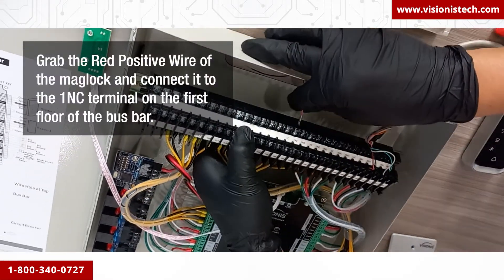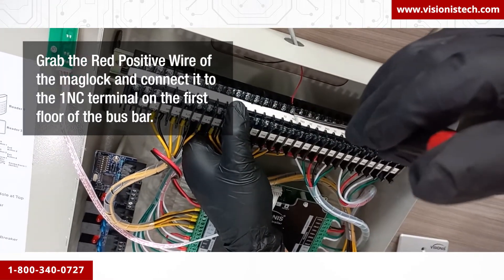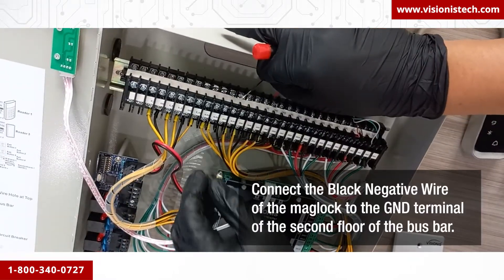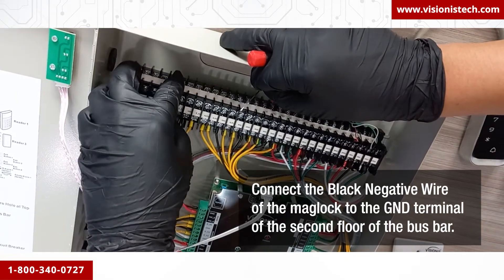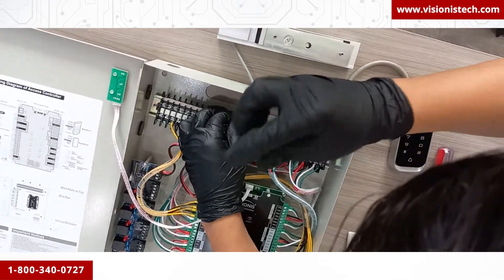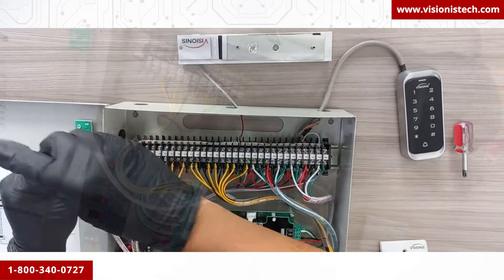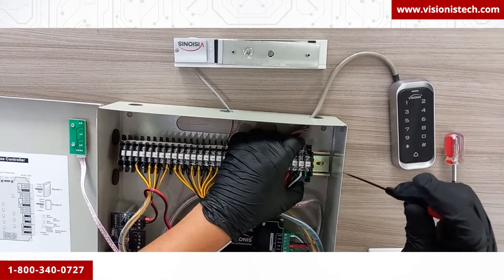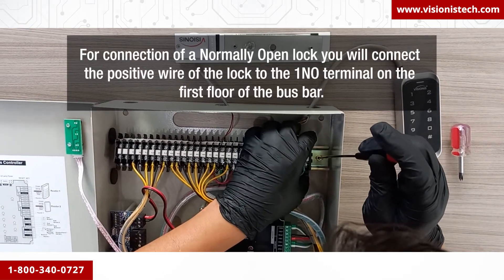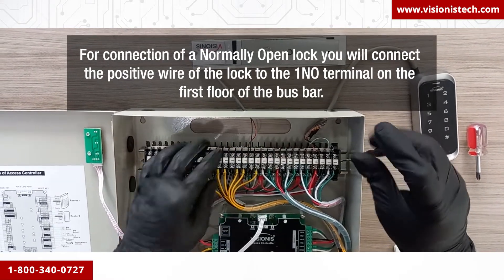Grab the red positive wire of the mag lock and connect it to the 1NC terminal on the first floor of the bus bar. Then connect the black negative wire of the mag lock to the GND terminal on the second floor of the bus bar. When you finish the connections, you can put the bus bar back into the cabinet. For connection of a normally open lock, connect the positive wire of the lock to the 1NO terminal on the first floor of the bus bar.